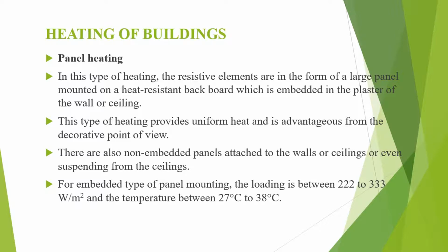For the embedded type of panel mounting, the loading is between 222 to 333 watt per meter square and the temperature is between 27 degrees Celsius to 38 degrees Celsius.